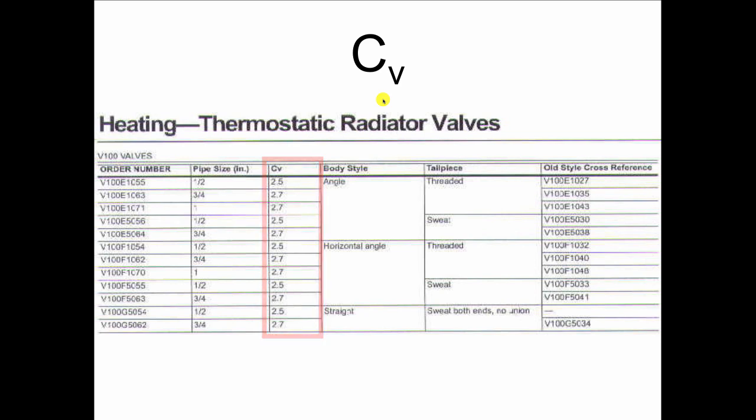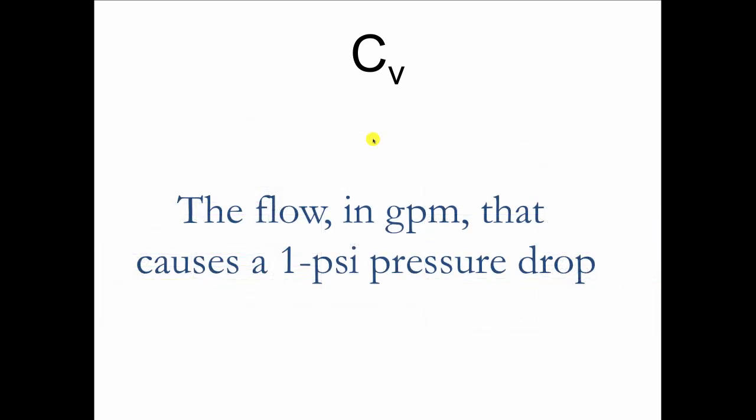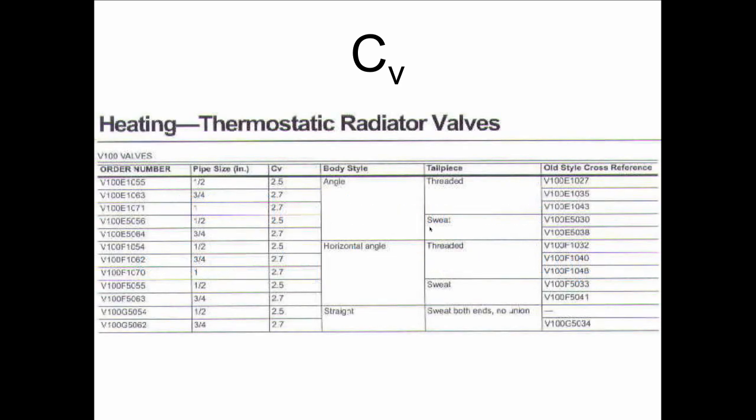CV is an engineering term and CV is always read as a number. And what it is is the amount of water in GPM, the flow of water in GPM that causes a one pound pressure drop across that valve. The CV you'll see pop up in a lot of things. It's given for packaged equipment. It's given for all kinds of valving. And once we know the pressure drop at one PSI we can figure out the pressure drop at any flow rate or the flow rate at any pressure drop.